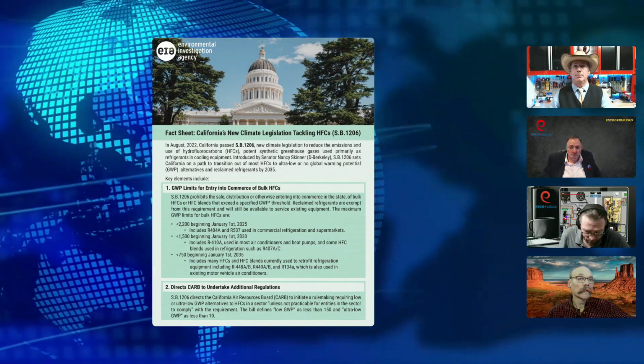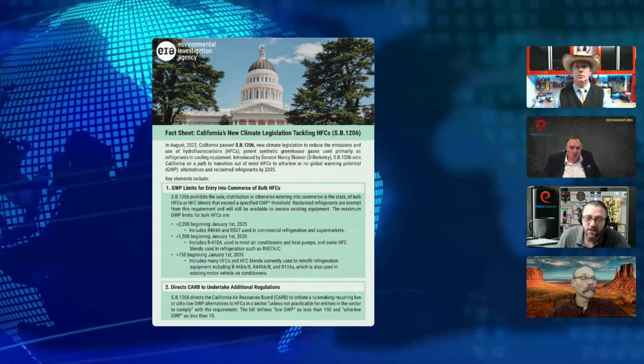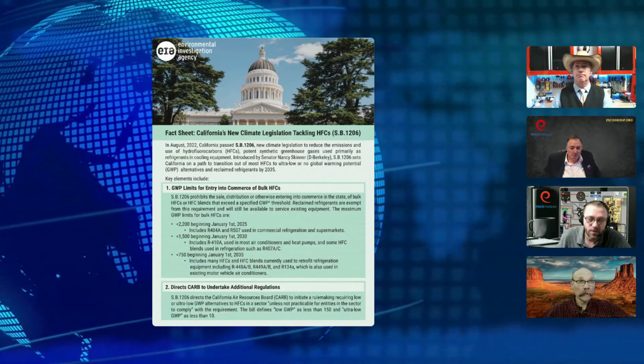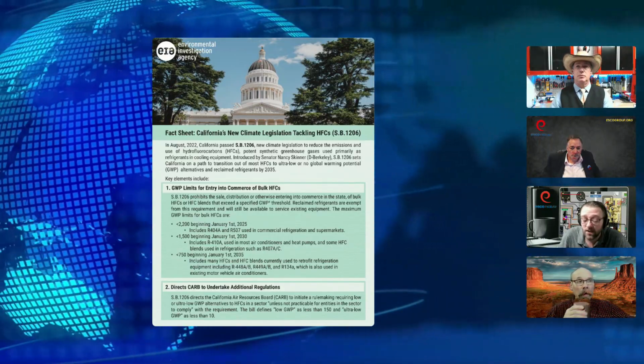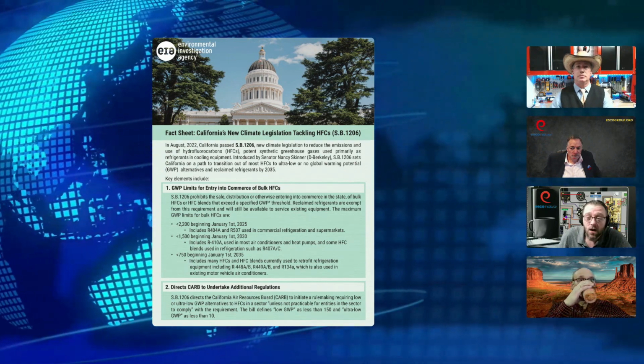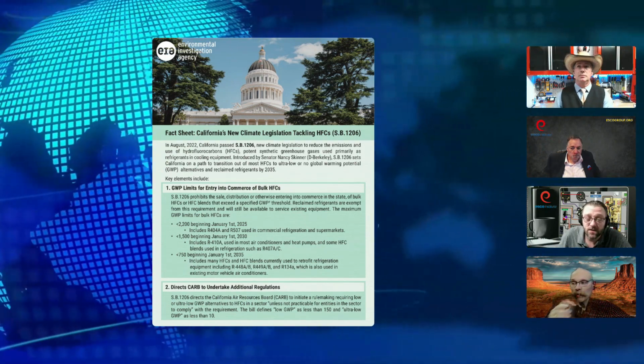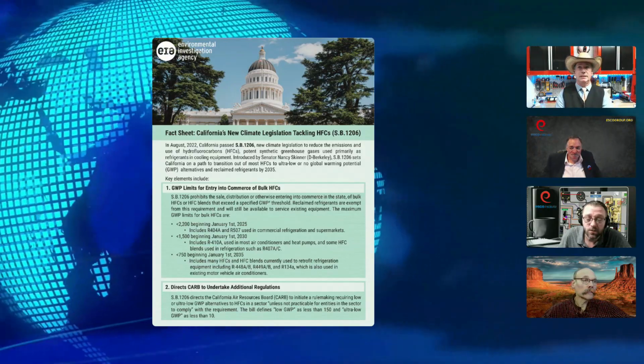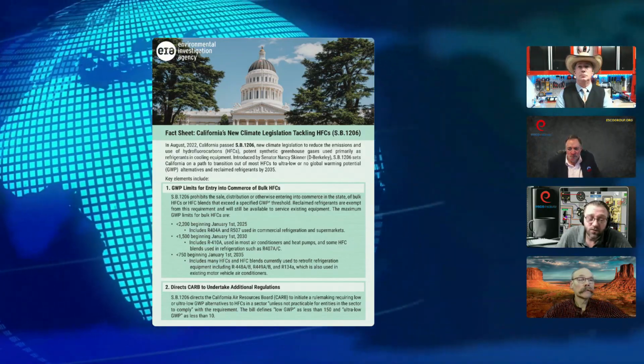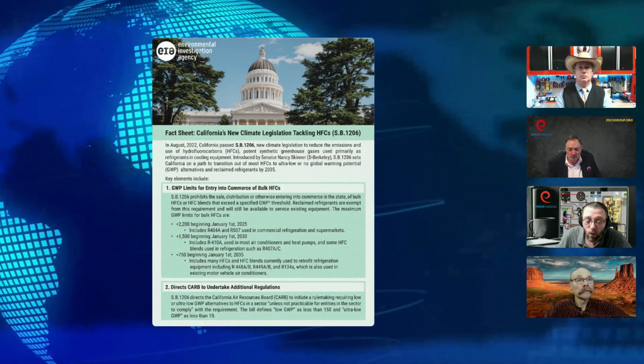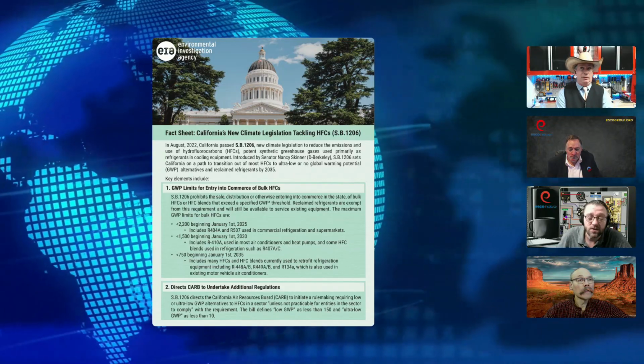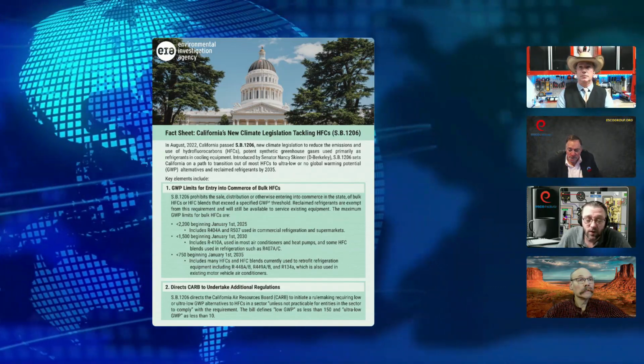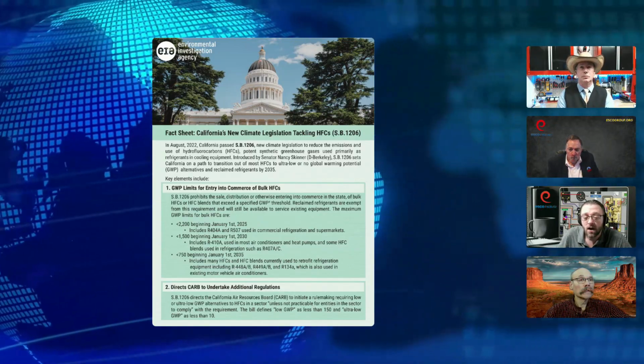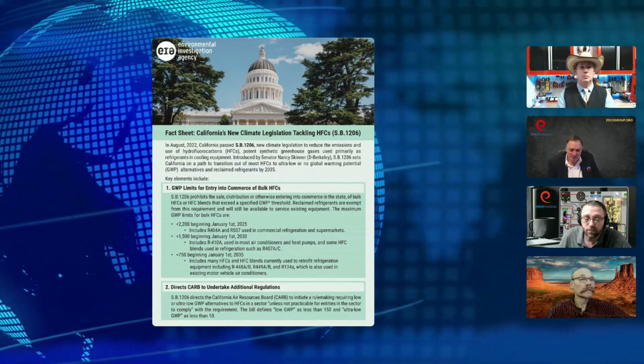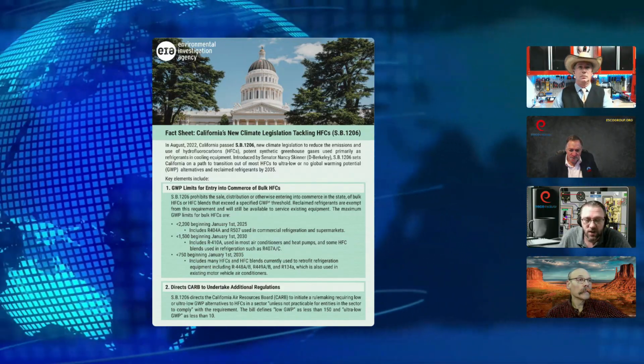Basically, this means you can't bring in tanks of refrigerant that exceed those GWPs on those dates. Beginning January 1st of this year, you're not allowed to bring 404A into California to put into commerce or into a unit. At 1,500 GWP in 2030, you won't be able to bring in a virgin tank of 410A to service your legacy 410A equipment.